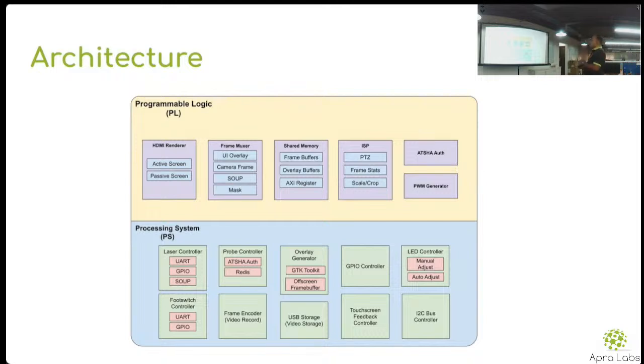Inside Zynq, we have two partitions, you can say. One partition is ARM, and the other is for logical processing, like ISP and all. Our ARM was controlling the laser. It was getting inputs from the foot switch controller, and based on that, sending laser commands to provide an intensity, like how much the intensity of the laser should go, and treat that eye.